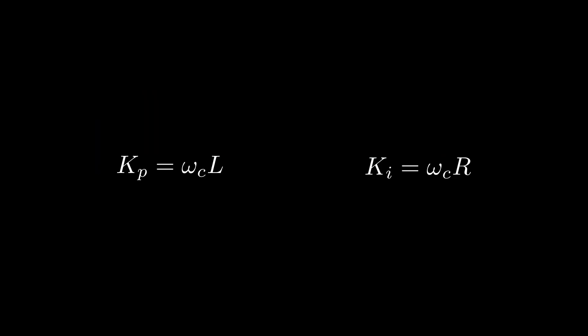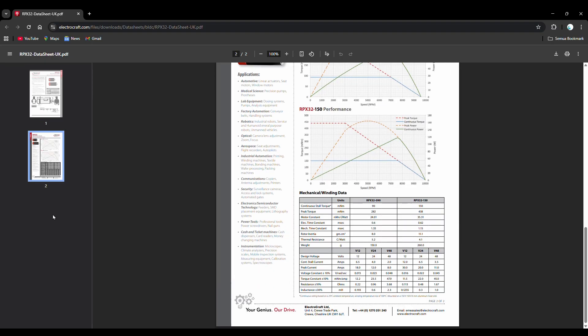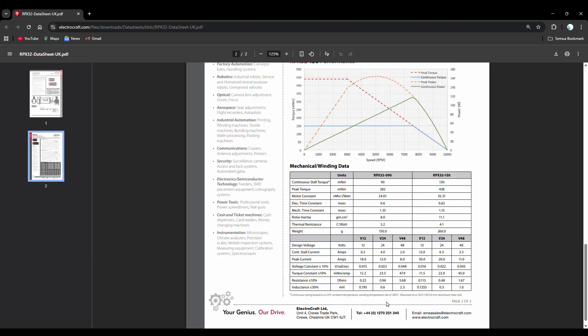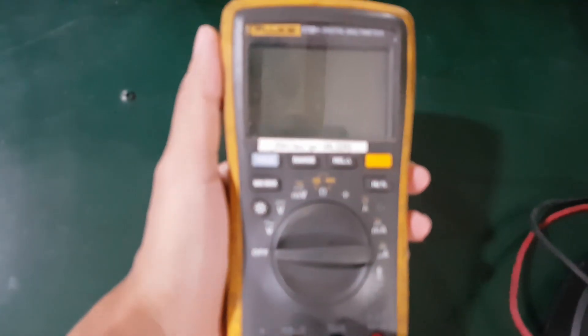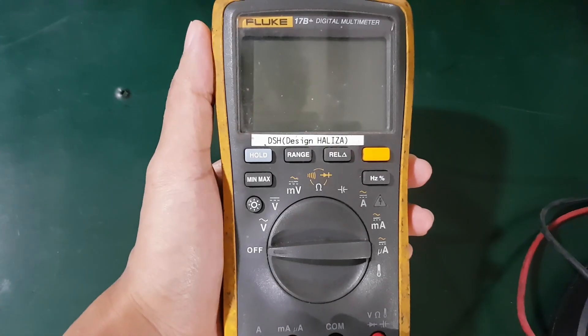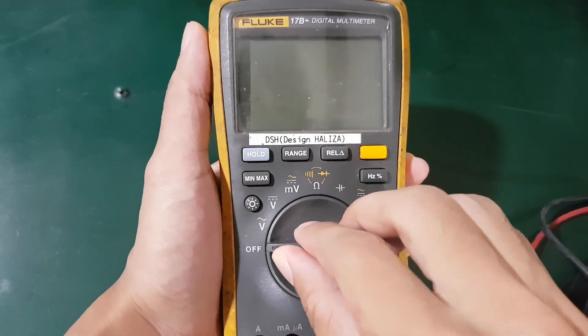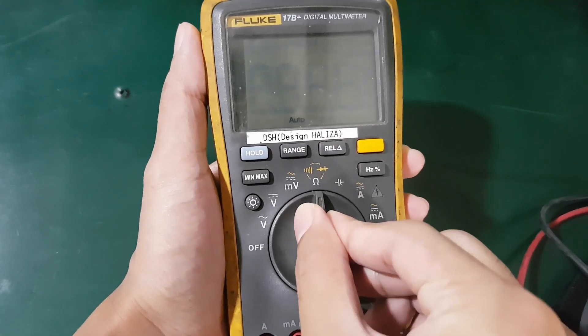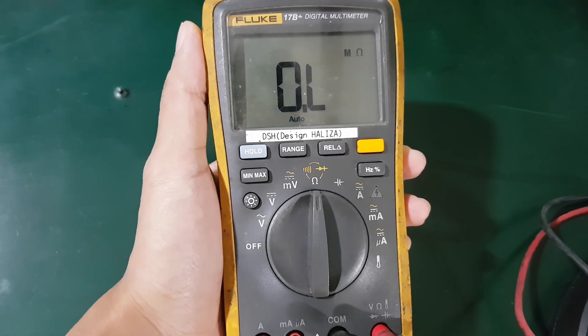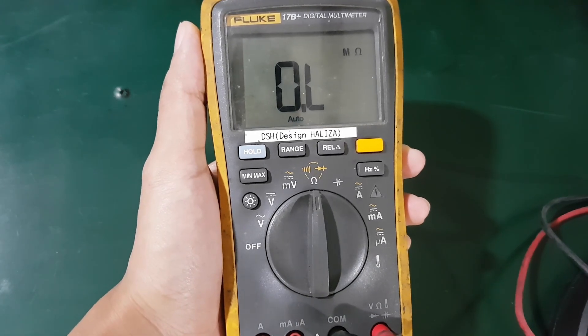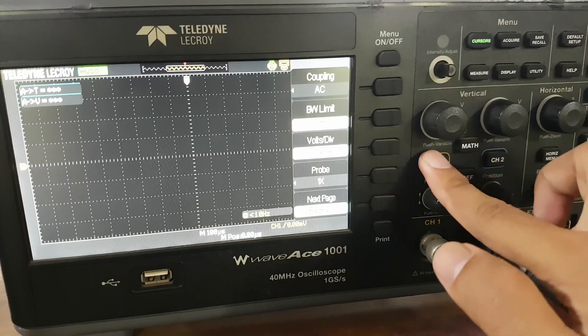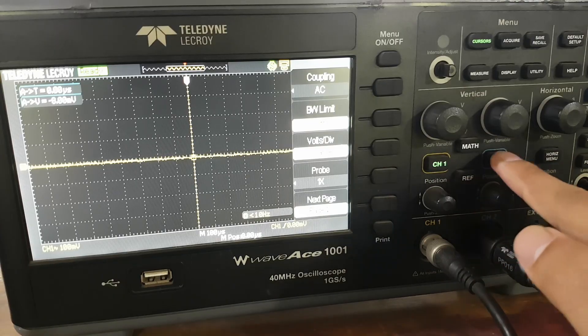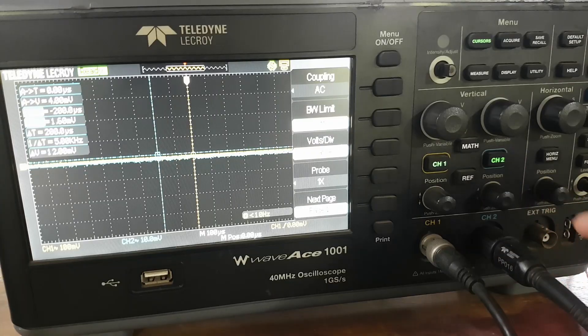After understanding bandwidth, we just need to input the motor's resistance and inductance values so we can obtain the desired KP and KI values. Some motors list these resistance and inductance values in their datasheets. But if not, we need to measure them manually using an accurate RCL meter. If you don't have one, there is an alternative way to measure the motor's R and L values using a function generator and an oscilloscope, as I will do to measure my motor here.